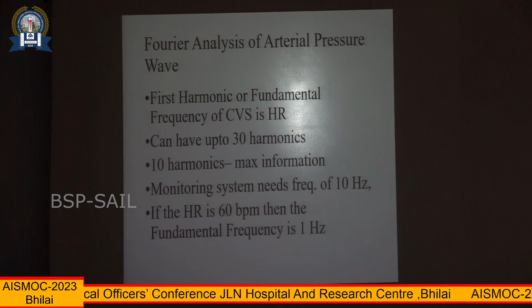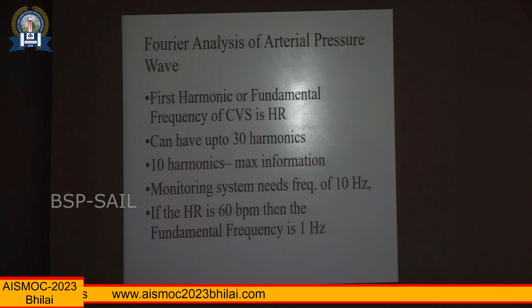So ideally the monitoring system frequency has to be anywhere between more than 10. Normally we have almost 25. Okay, so the monitoring, so that you do not get the frequency of the system and the frequency of the arterial trace to coincide and cause resonance. Okay, you must have heard the story of the soldiers marching on the bridge, and when the marching frequency matched the frequency of the bridge, it collapsed because it causes increase in the resonance of the system. Okay, so that's why you want the monitoring system to have a frequency way higher than what the frequency of the arterial trace is. Okay, good.